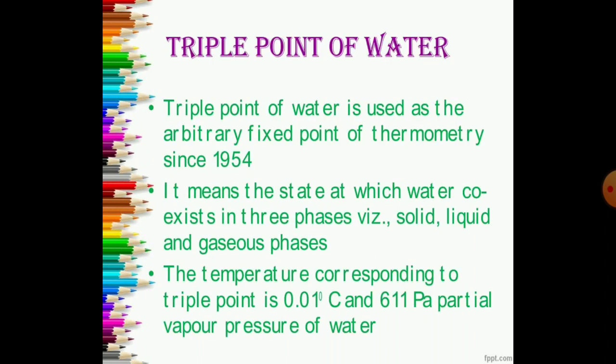The triple point of water is used as the fixed point of thermometry. It means that water coexists in three phases: solid, liquid and gas. The temperature corresponding to the triple point is 0.01 degree Celsius and 611 pascal vapor pressure of water.